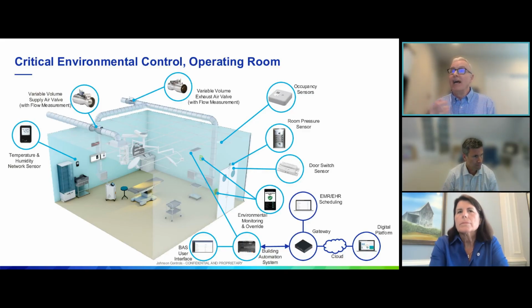Another side of that for humidity is that, obviously, within these spaces we don't want any type of condensation. So that's a real critical part of this, and that's something that we report into our compliance. As we start working our way around clockwise, you'll see those two metal cylinders with the red circles around them. What those are, if you're not familiar with them, are air valves. Similar to what a VAV box may do, these are really regulating the supply as well as the exhaust within that space. So these are very critical parts of this critical environment.